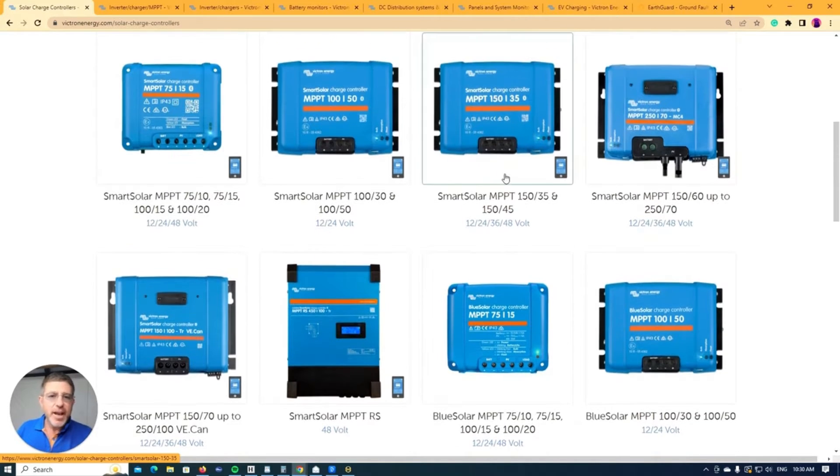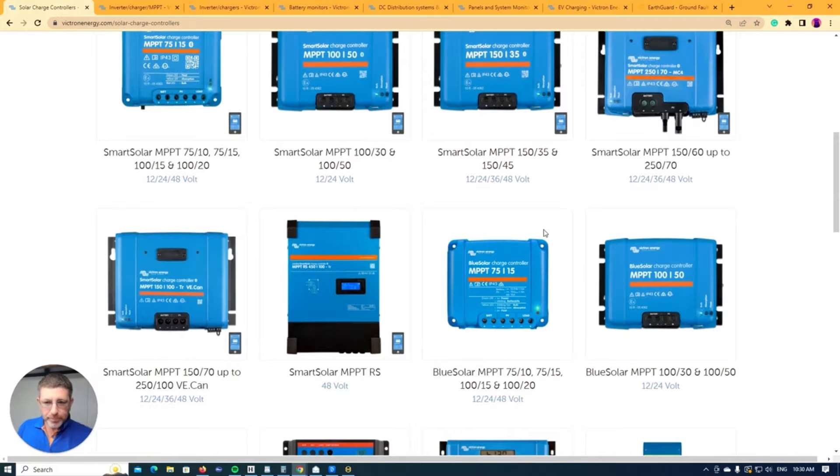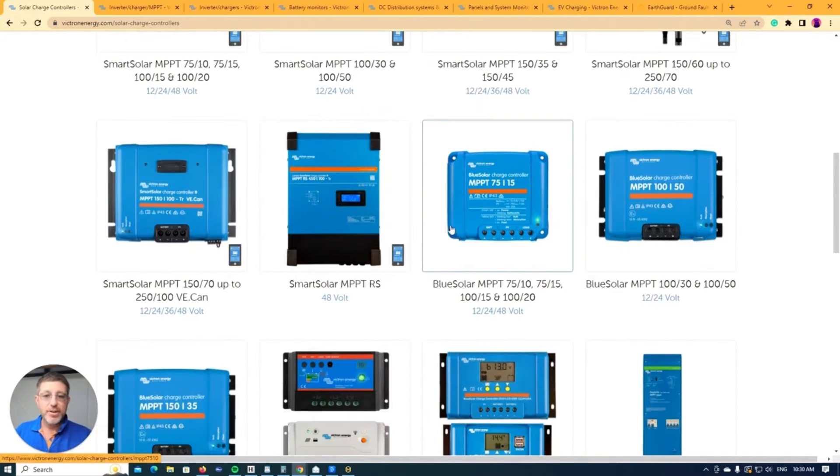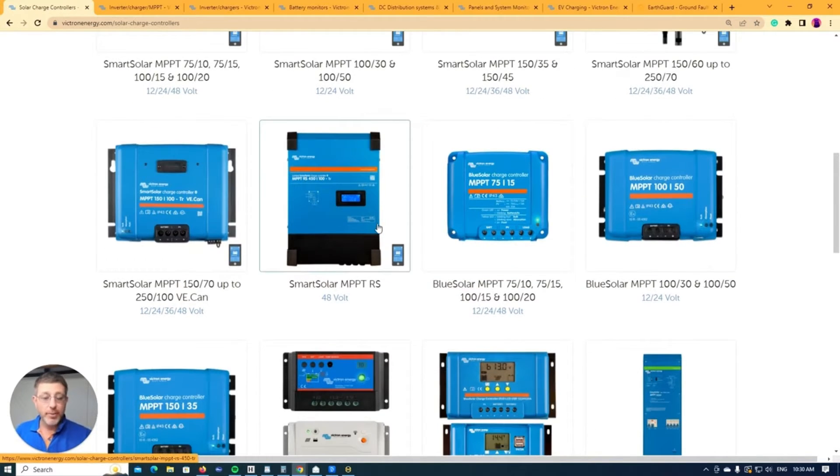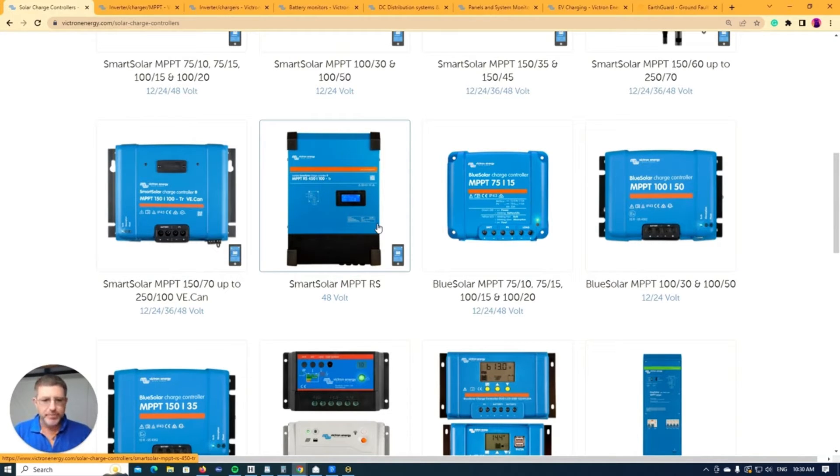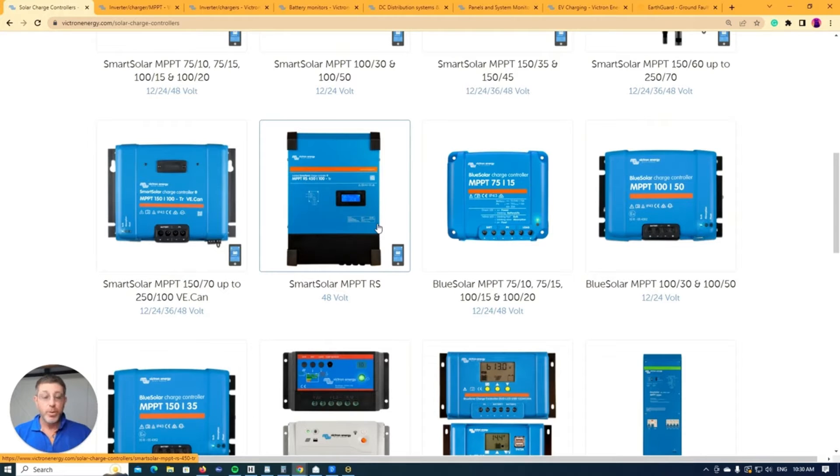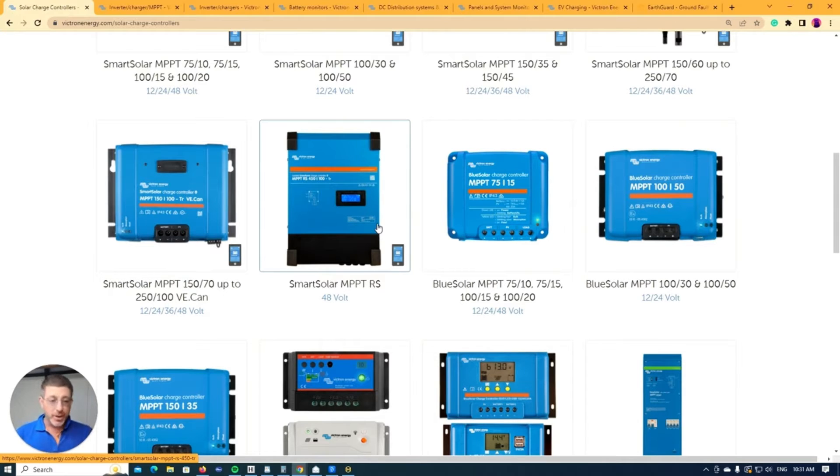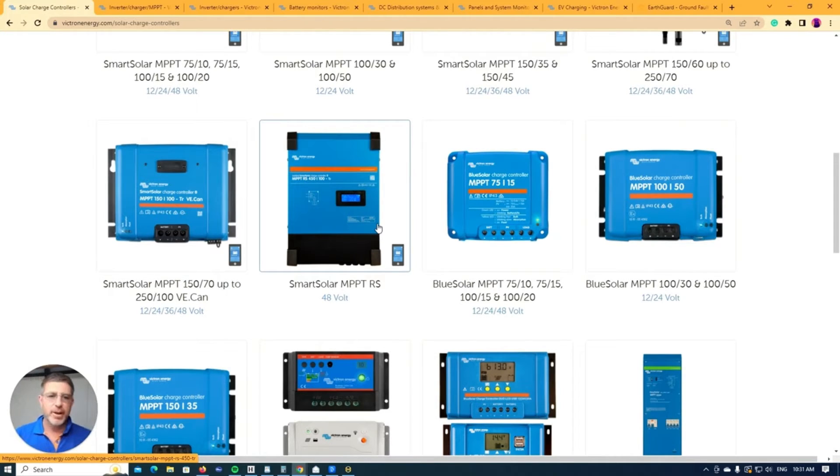Now in Australia, as an example, we're not allowed to use all these MPPTs. We have to use a lot of the higher ones when we're installing for customers because they have to have an earth fault alarm built into them. And it all really depends whereabouts you are in the world or what voltage you're able to play with. So just take into consideration what you can and can't do in your country with these Victron products.